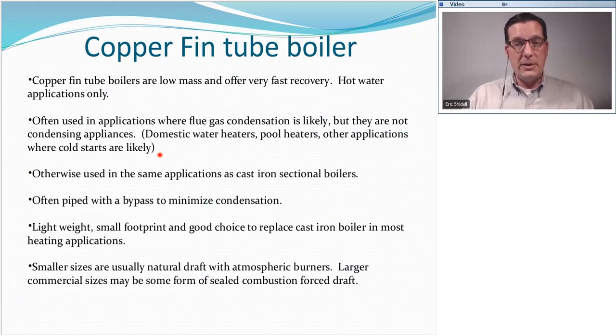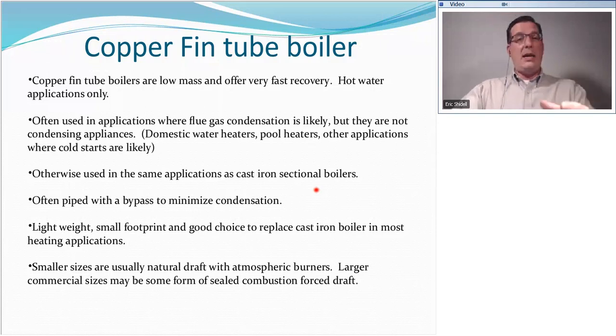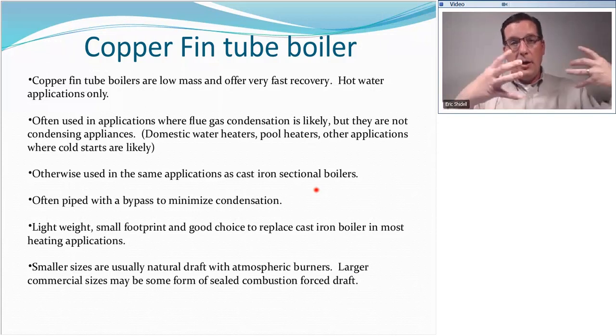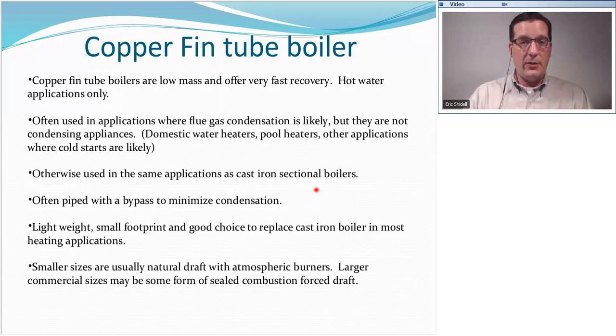Some examples where condensation could be likely, especially on light off, would be as a domestic water heater or as a pool heater, or any other application where cold starts are likely. And they're good in that application because the copper itself won't corrode unless we let things get away from us and run them condensing all the time. Otherwise, they're used in the same applications as cast iron boilers. In fact, we could take that big, heavy, old cast iron boiler out and put in a properly sized copper fin tube boiler, and that system would be happy for a very long time.